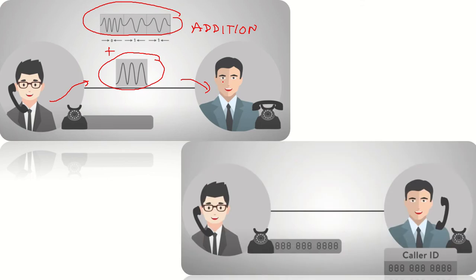Now, what happens if you mix the Bell 202 modem standard with your analog signal? It gives additional information. This feature is already available in your phones — it is called caller ID. The original analog transmission takes place, and along with it the caller ID, which is digital information, is also transmitted. This digital information is added to the analog signal. Most importantly, this digital signal will in no way affect your actual analog signal.